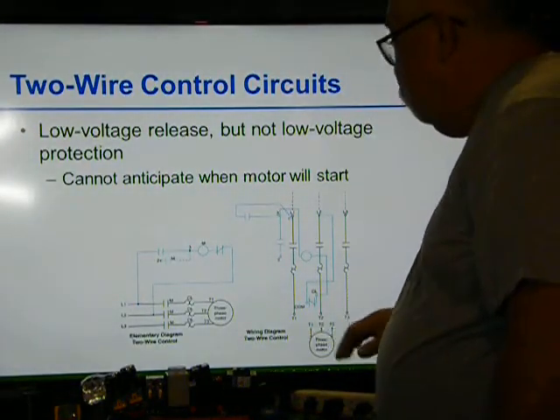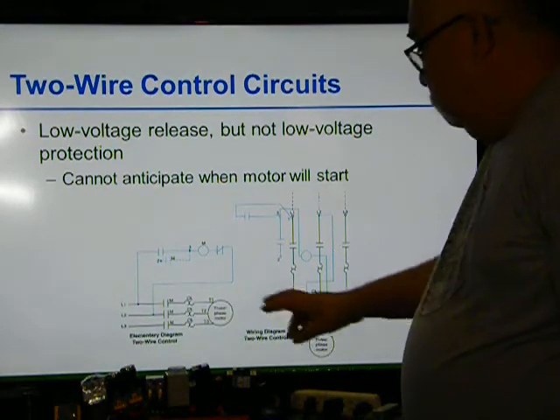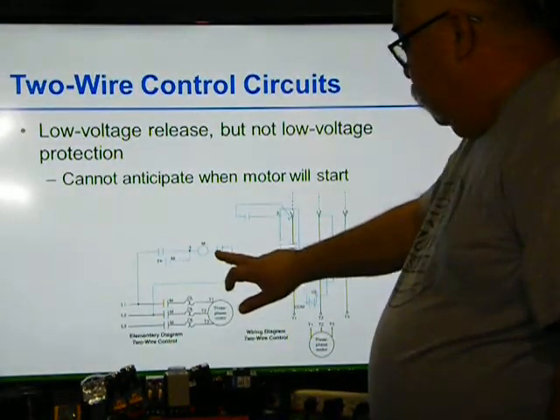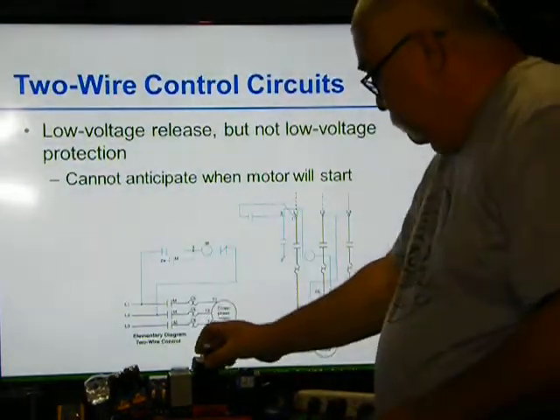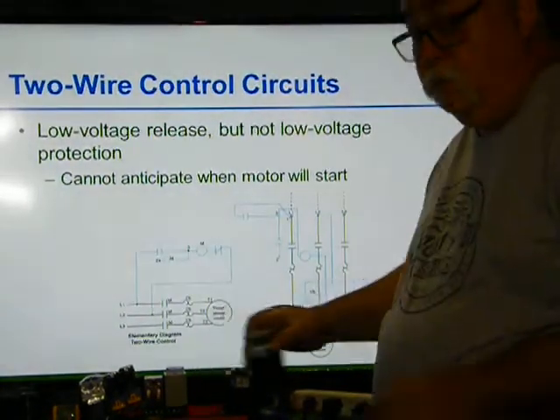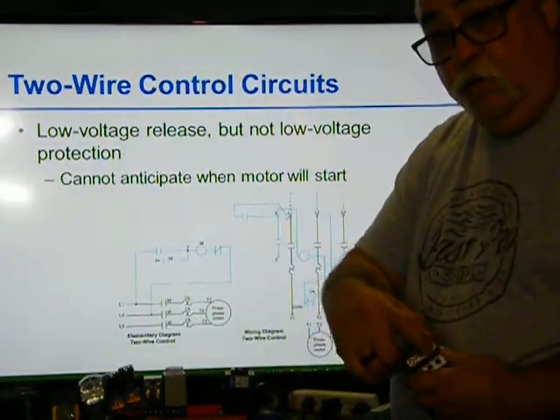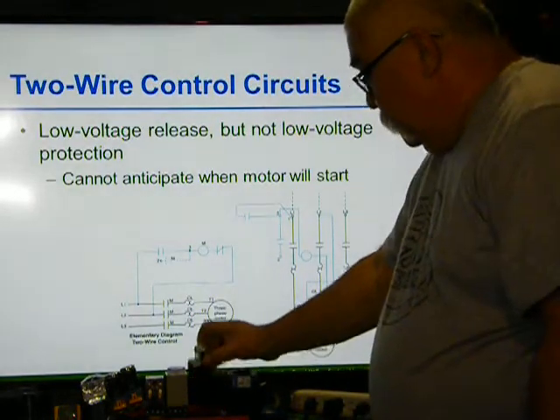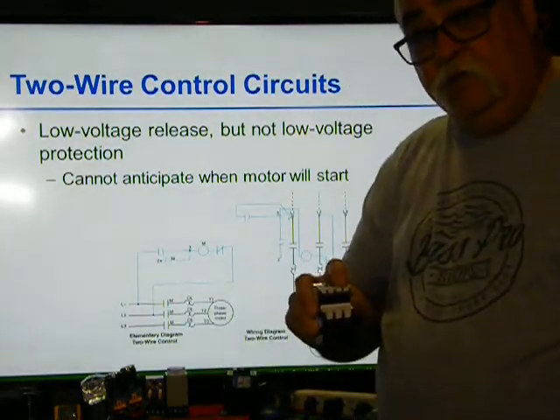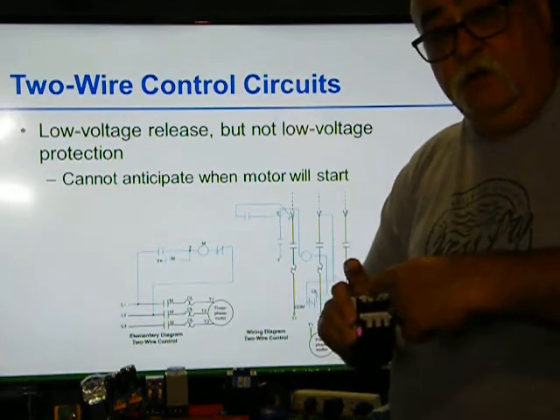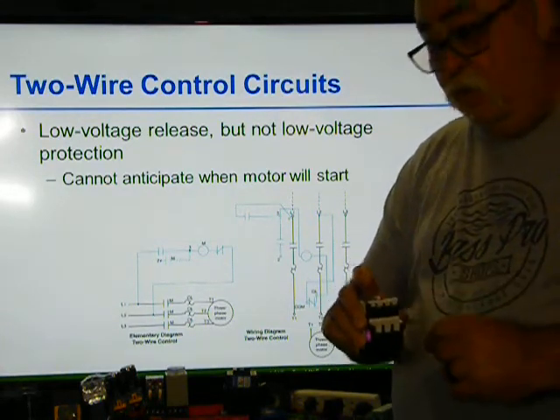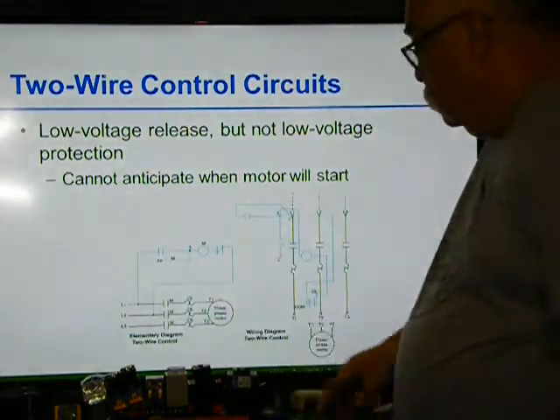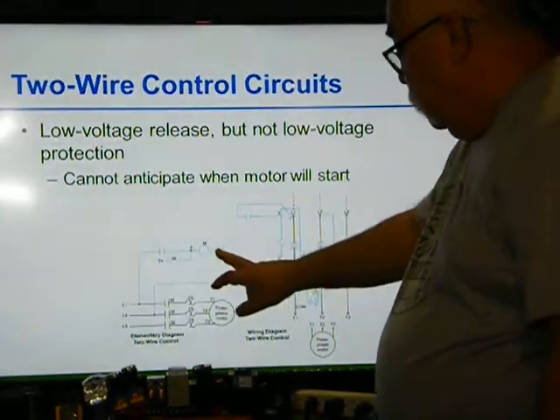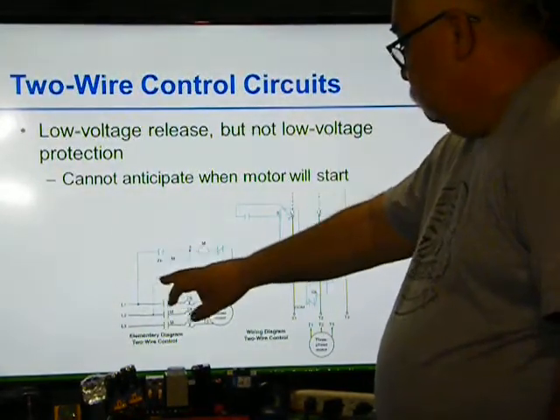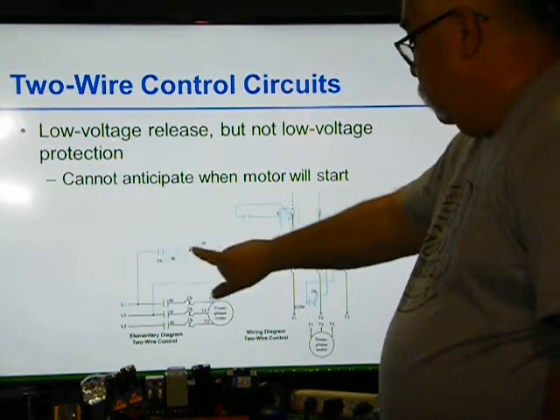Okay, so this is a two-wire control circuit. Power comes off to one contact, but it's always closed, and this would be here on my overloads. This one gives me the option of normally open or normally closed. Let's say I've got two motors. When that one turns off, it turns this one on, and that's why it goes to the normally open. And then here is my switch. Turn it on and off.